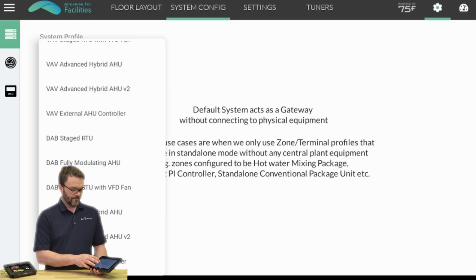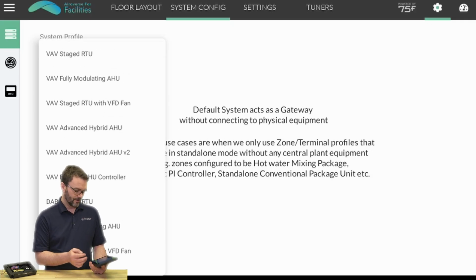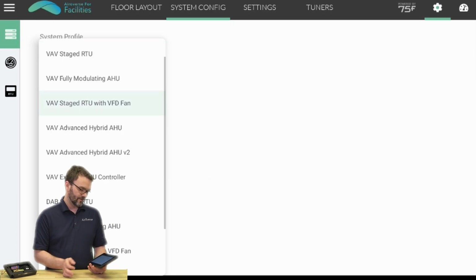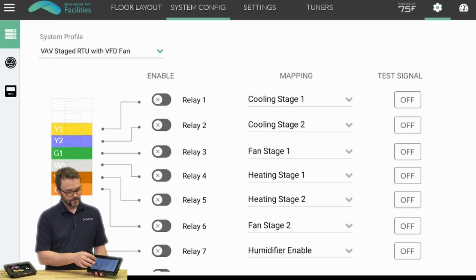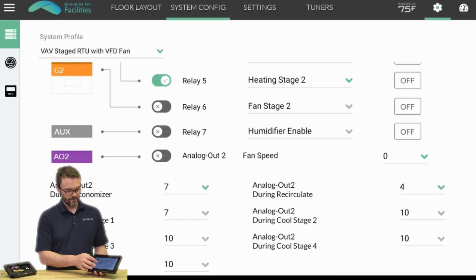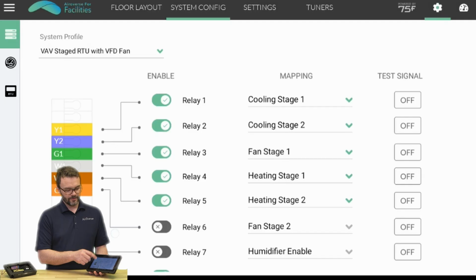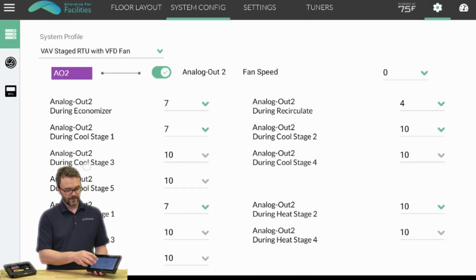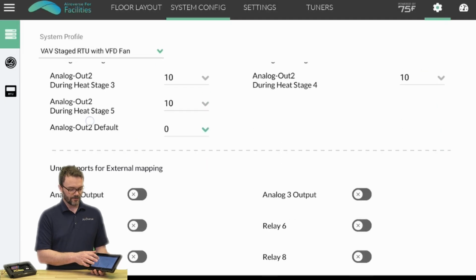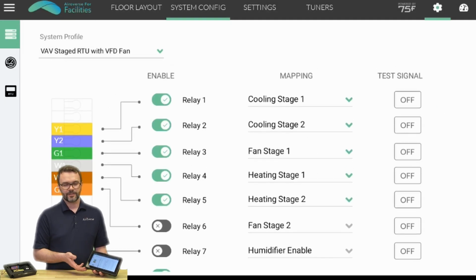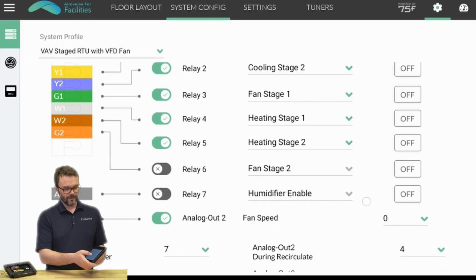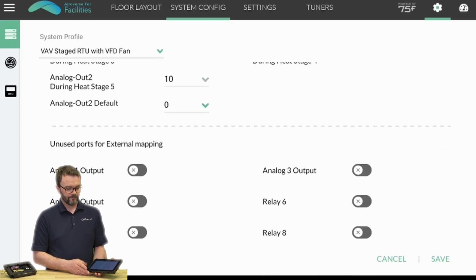So we're going to choose a VAV staged RTU with VFD fan. Here we see our options for what pieces of equipment our AHU is going to have. Since I chose a staged unit with a VFD fan, it restricted my options and gave me additional options for how to treat fan speed during different stages. This isn't a traditional VAV system by any means, but it comes up quite frequently.